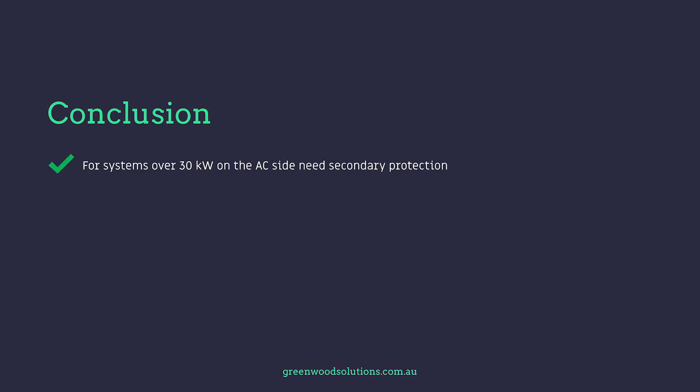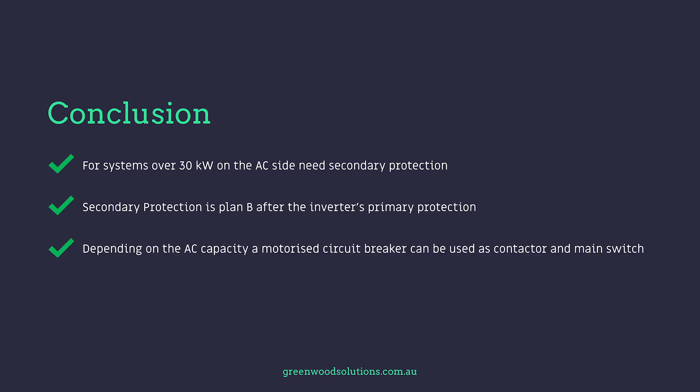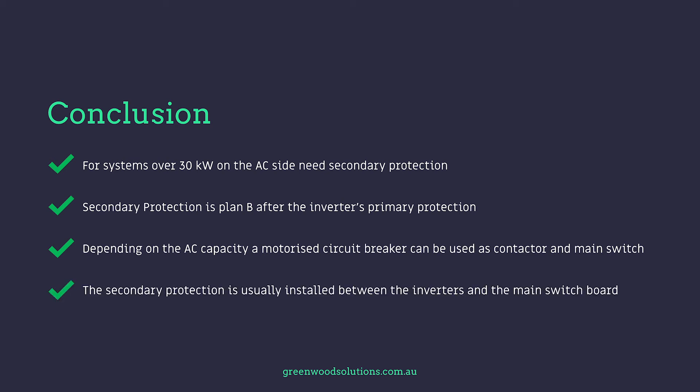Conclusion: systems over 30 kilowatts on the AC side will need secondary protection. Secondary protection is plan B after the inverter's primary protection. Depending on the AC capacity, a motorized circuit breaker can be used as contactor and main switch. The secondary protection is usually installed between the inverters and the main switch board. Thanks for watching our presentation on secondary protection boards. If you have any questions, inquiries, please feel free to drop us a line. Thanks very much for watching.